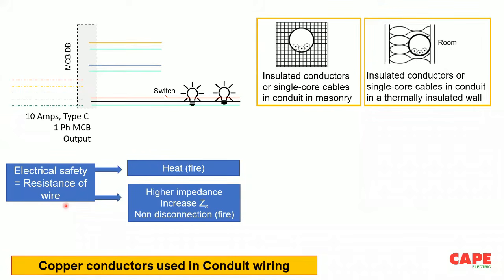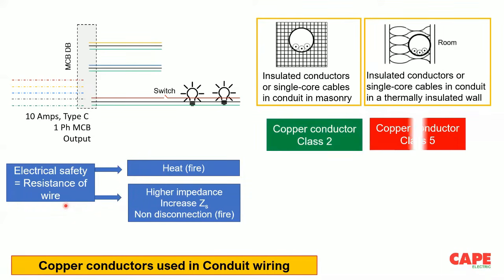conductor resistance is important, because if the resistance of the wire is high, more heat is produced. In that particular case, wires are classified into class 1, 2, 5, 6. Class 5 and 6 are flexible wires. All the calculations in the standards are made based on copper conductor class 2.